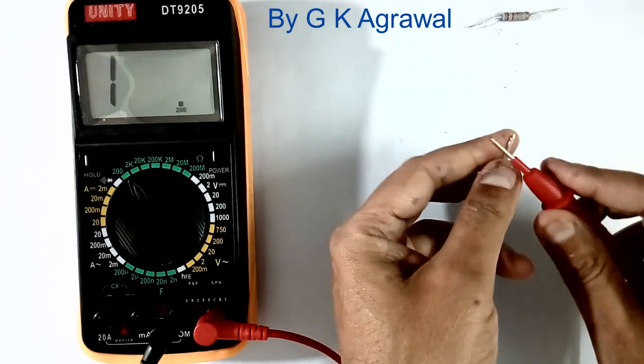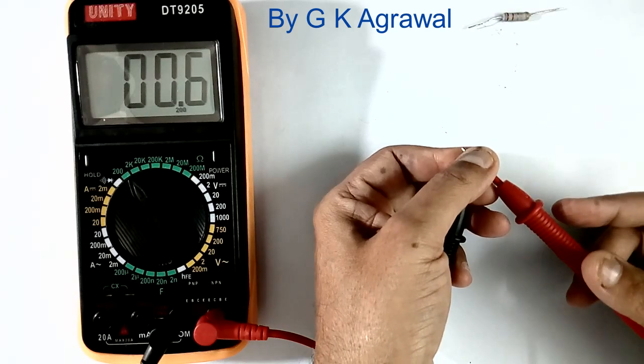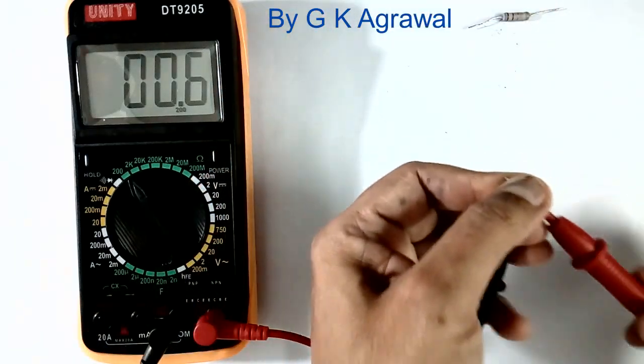Now if I remove the resistor and short this lead, it is showing 0.6 ohms. This 0.6 ohms is the resistance of this lead which is always added to the resistor.